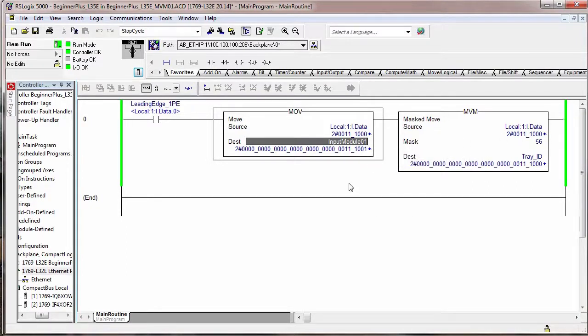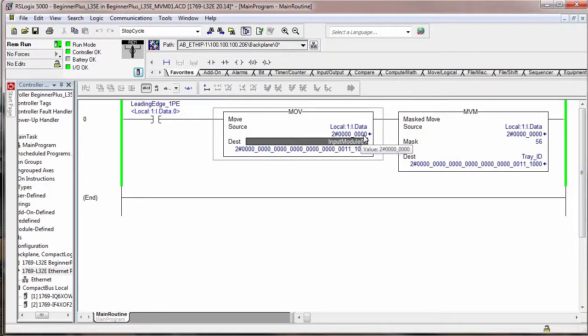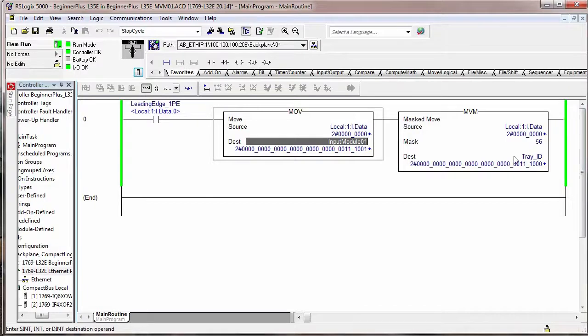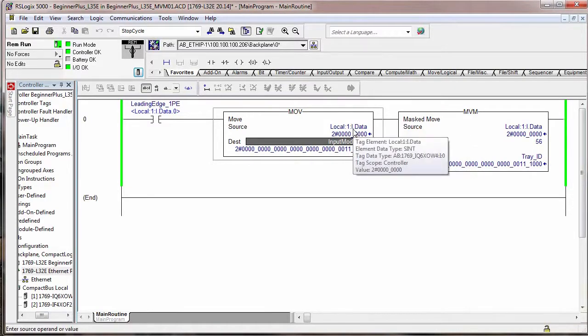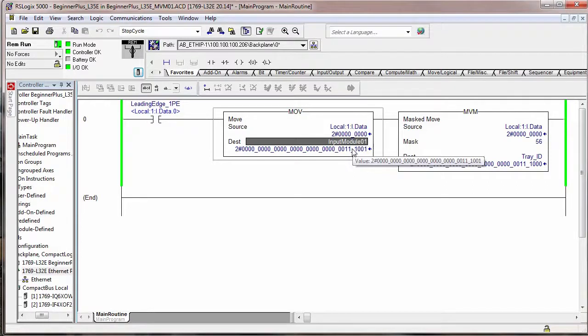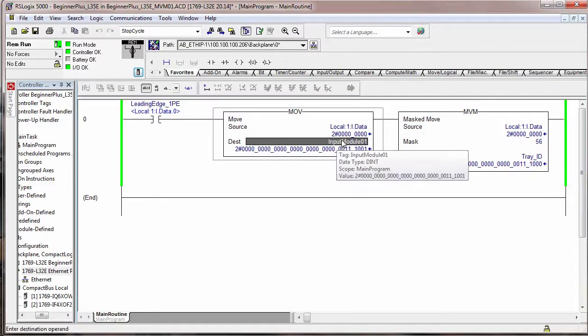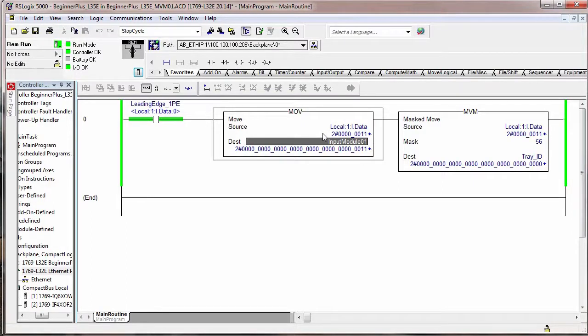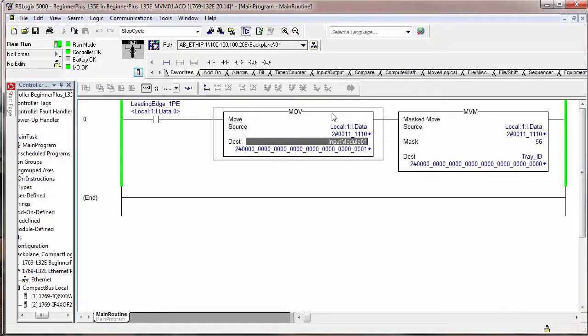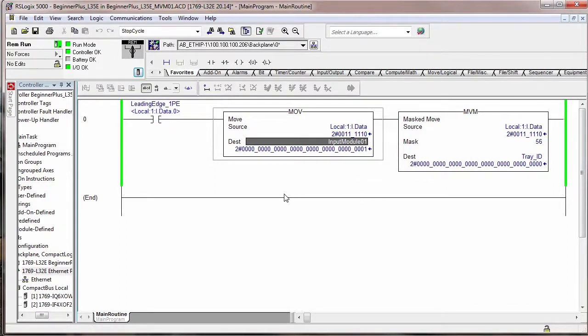This allows us to compare the bit pattern between the input module and the destination for both of these. Now I'm going to turn all of those inputs off. So you see that the value up here, and remember that we're only working with three of these bits. We're going to work with four, five, and six, which would be these three right here. But we could actually turn any of these on. You might be looking, saying, well, why is the source and the destination different for this instruction? Well, this rung is not true. So as I change values in this input word, I'm turning values on and off. But if I turn on any of these others, notice that these values are not seen down here, simply because that input is not on. So this rung is not true and it's not executing either one of these.